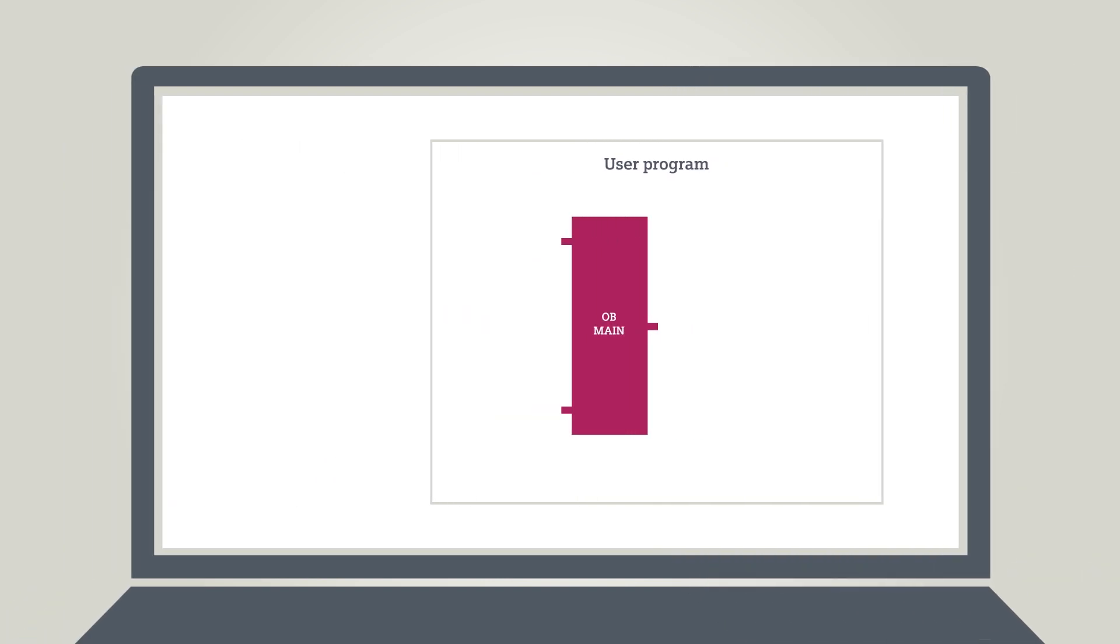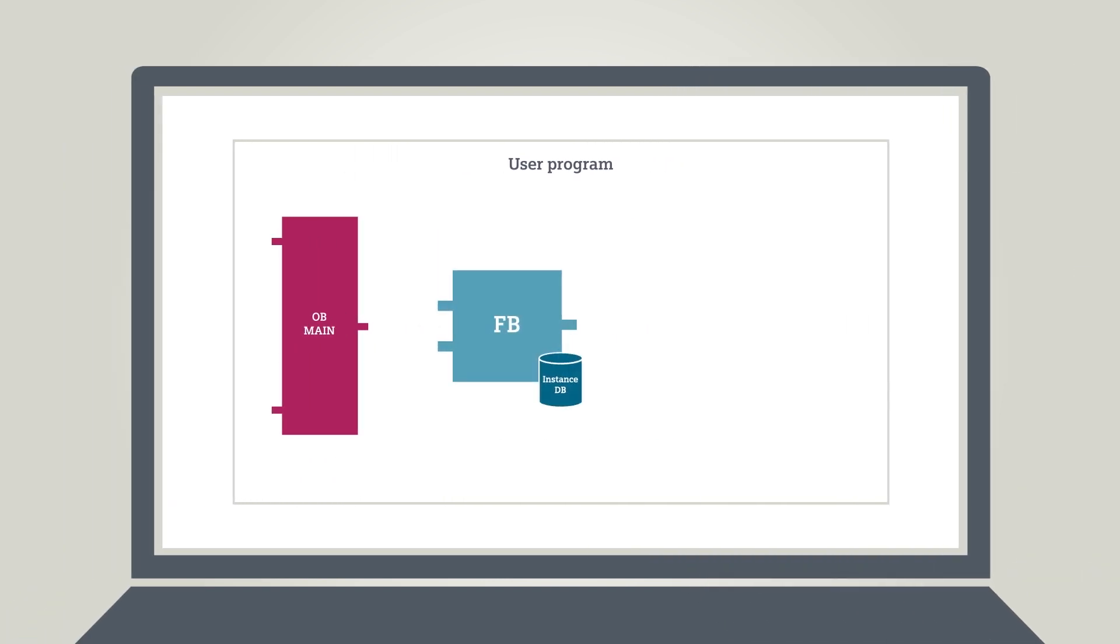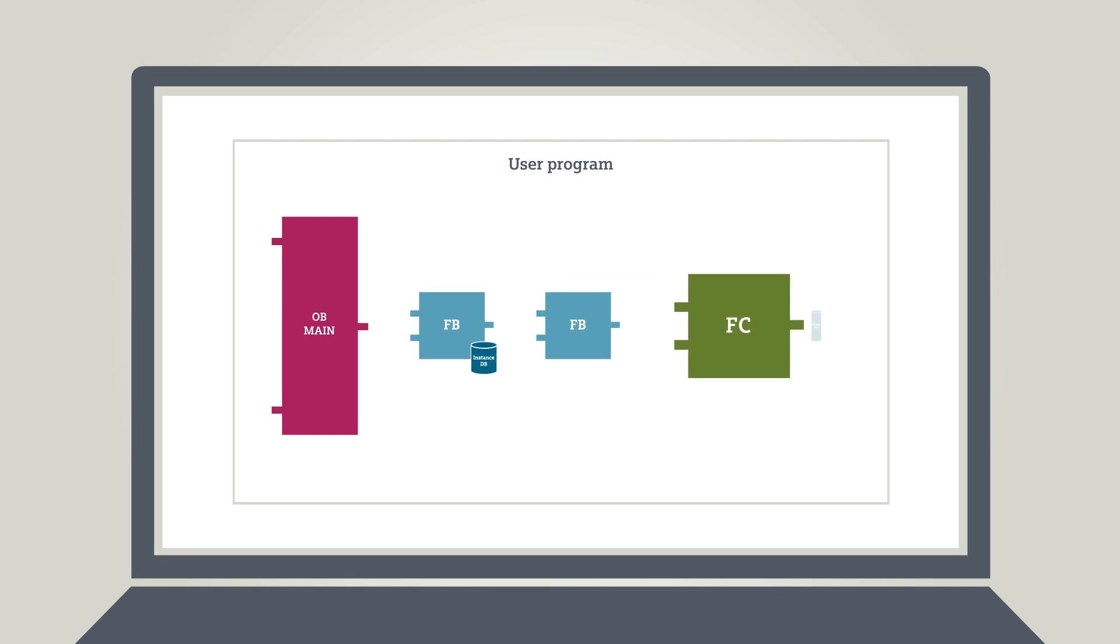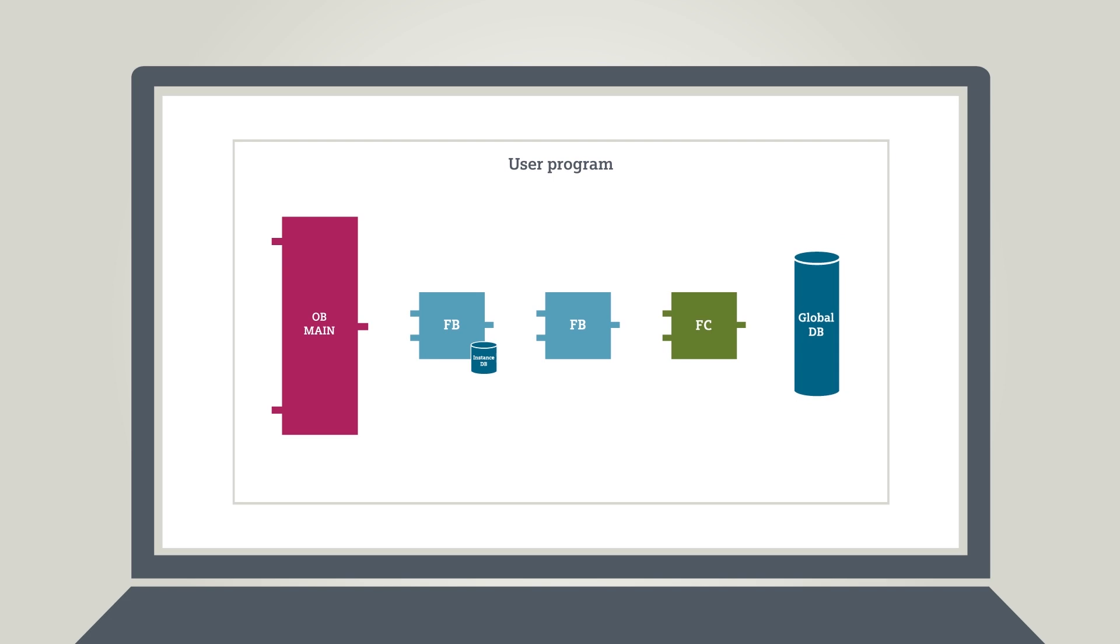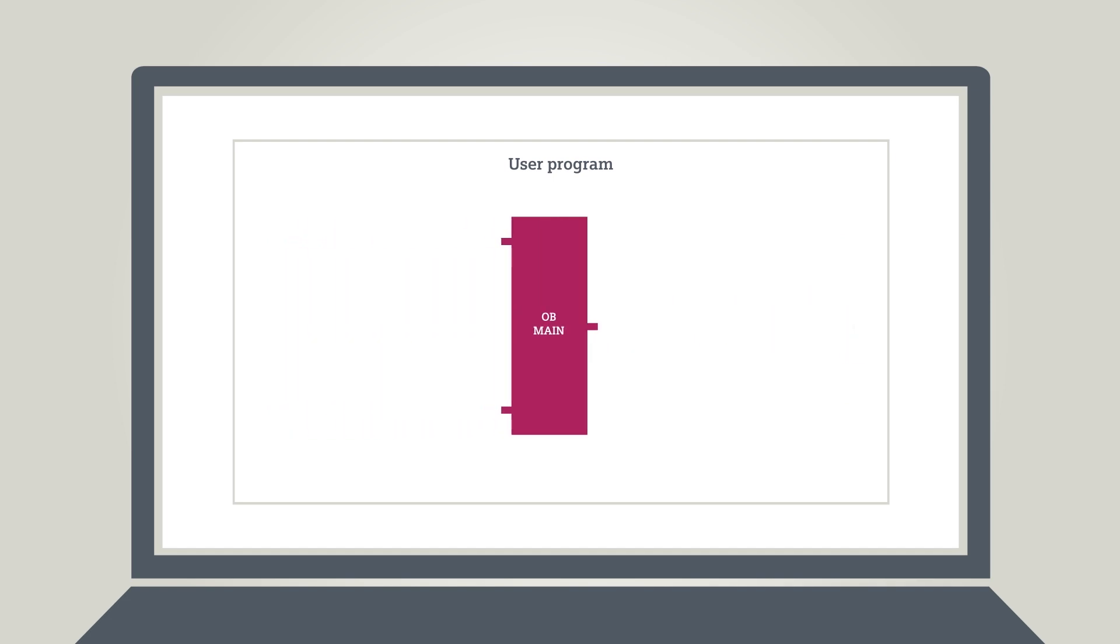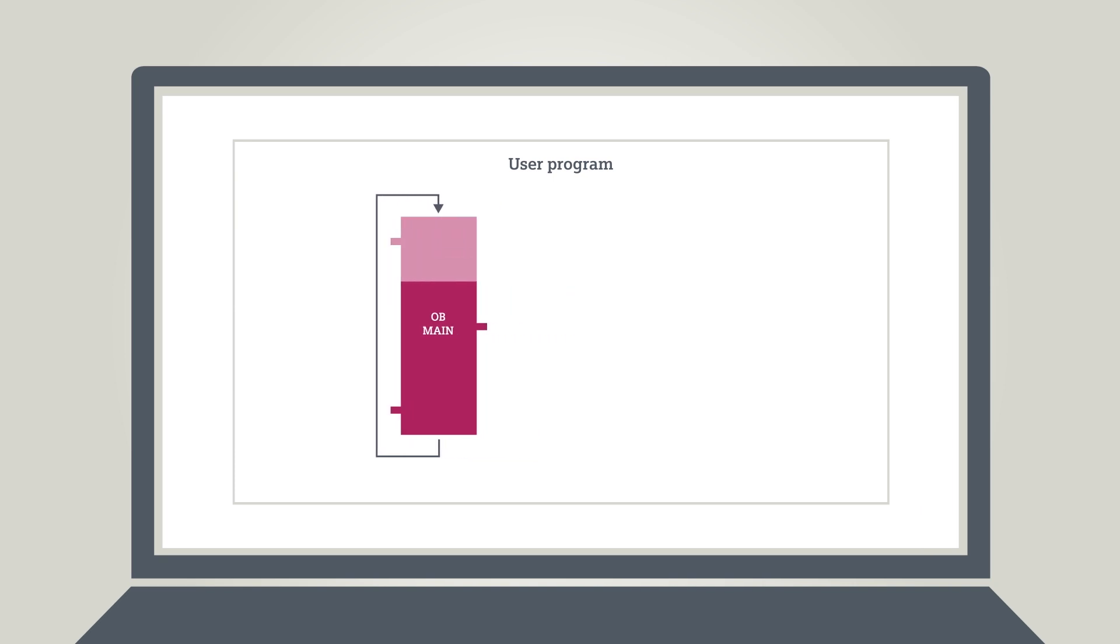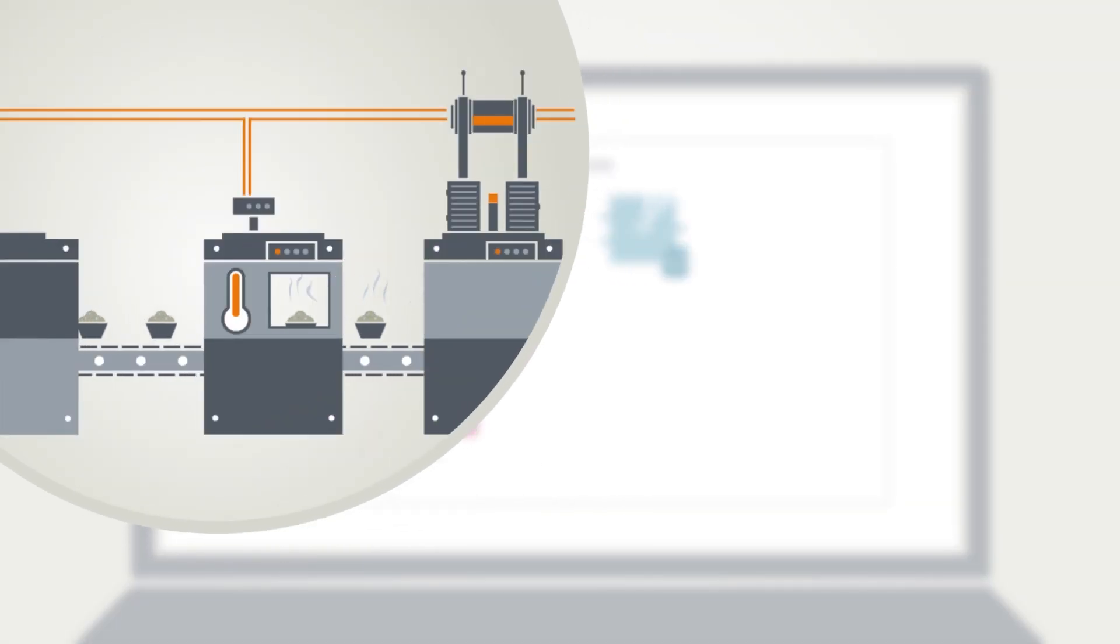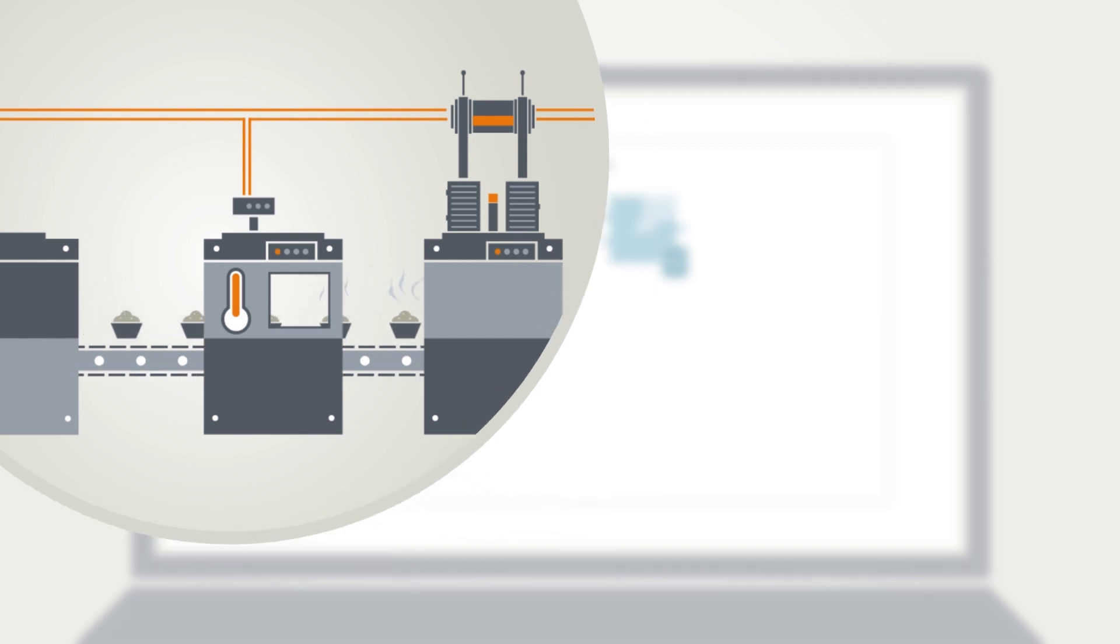In an effort to avoid all that, the TIA Portal offers various block types for the encapsulation of your subtasks depending on requirements. The main program is generally stored in the cyclically called organization block OB-Main. OB-Main will then call up the corresponding unit, such as the technical unit of the first conveyor belt.